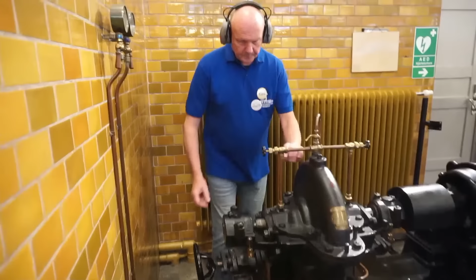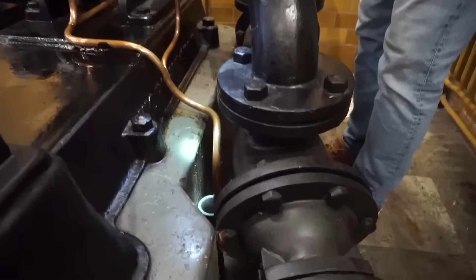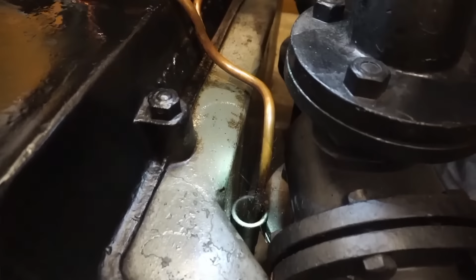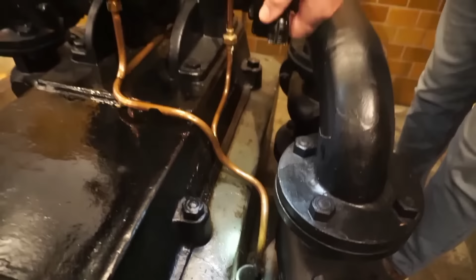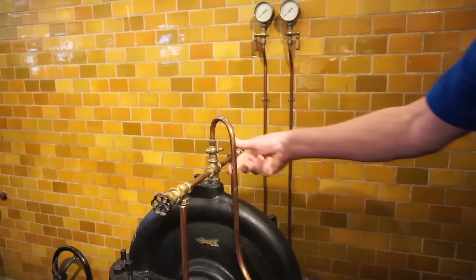Lasse is now opening the water supply, and is also opening a bleeding valve on top of the pump house to get rid of air pockets. When the pump is filled up with pure water and no more air is coming through the drainage pipe, he will turn off the bleeding valve, and he's going to start up the pump with a star delta switch, and the pump is running.